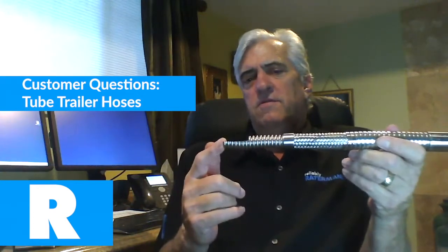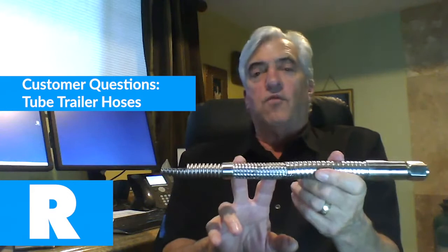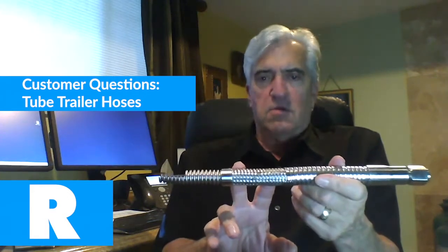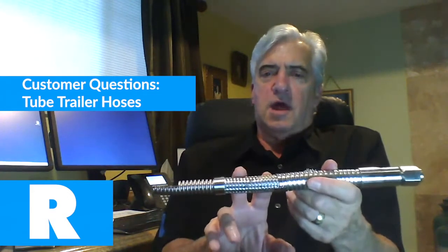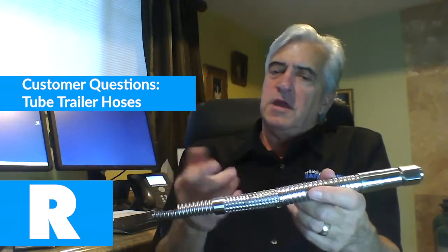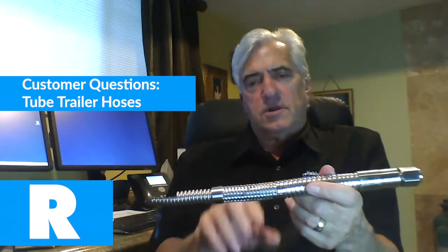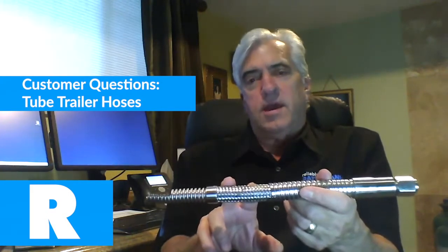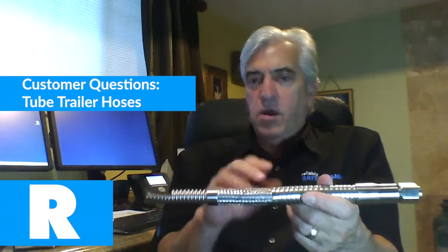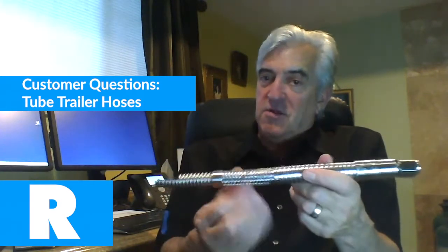So what you'll find is the tube trailer hose is quite different in that it has a Teflon liner inside of it, and instead of 2 layers of stainless steel, it's got 4 layers of stainless steel for 4,000 psi. The way to increase the pressure carrying capacity in a hose is to add an additional layer of stainless steel braid. This has 4. You go to 6,000, it takes it up to 6 layers, and it goes on and on.